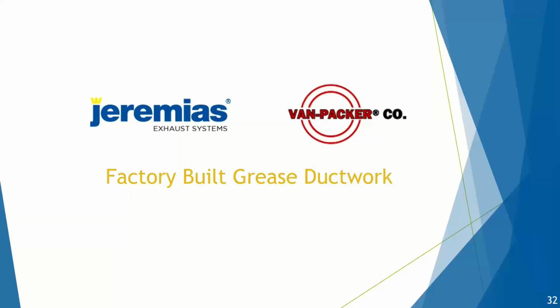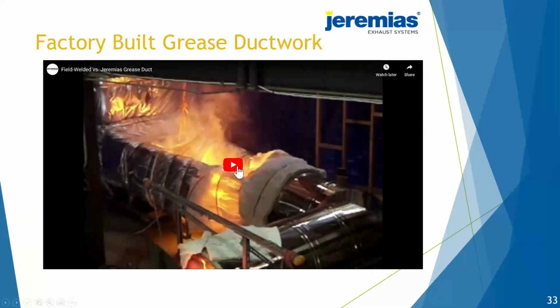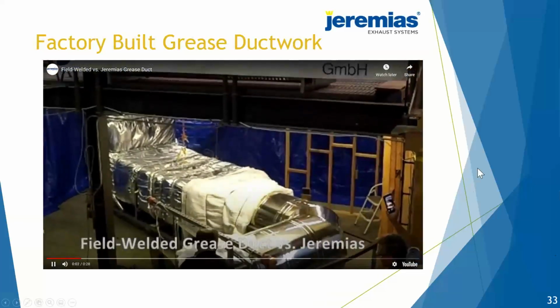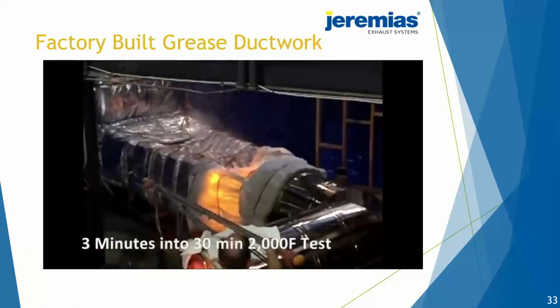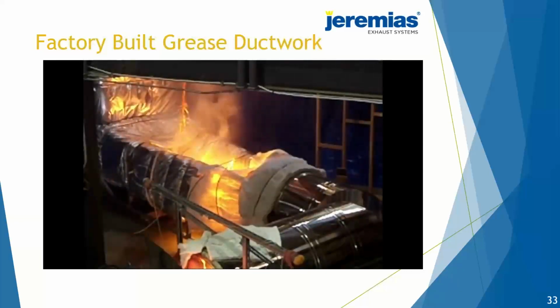So focusing in on some other Jeremias products and also Van Packer, we're going to look at some factory built grease ductwork. And I just want to show you guys this video real quick that shows a field built duct system during a 2000 degree 30 minute test. And you'll see how quickly this stuff breaks down. So this is 3 minutes into the test, and this is supposed to last at least 30 minutes.